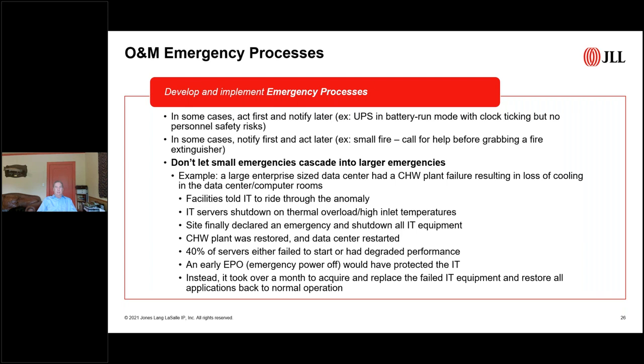If the building had done an EPO, an emergency power off, when the chill water plant first shut down and it became evident it may not be able to restart quickly, they could have protected the IT equipment. They would still have had an outage and an impact to their mission, but they could have restored that building within hours, maybe a day or two. Instead, they had to go find thousands of new servers, which they didn't have on the shelf. The suppliers didn't even have them. So it took over a month before that building was restored back to full operations.